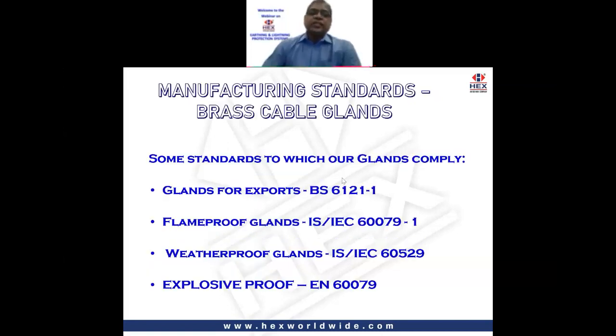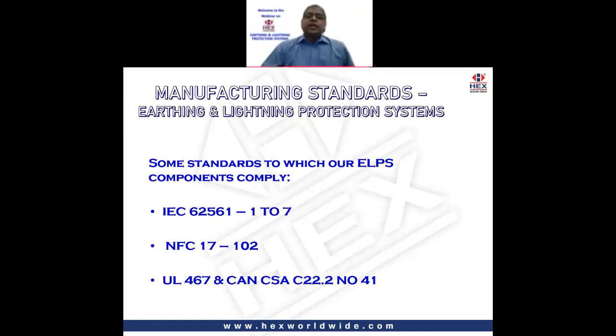Some standards to which our glands comply. BS 6121 is for glands that we export all over the world. Flameproof as per IEC 60079, weatherproof as per IEC 60529, and explosion-proof glands which we manufacture as per EN 60079. Some standards to which our earthing and lightning protection systems comply. IEC 62561 is the testing standard for IEC 62305. Then NFC 17 is for our ESE lightning arresters, and again UL and CSA for the UL product. Many people in India have been asking us to supply the products as per UL.